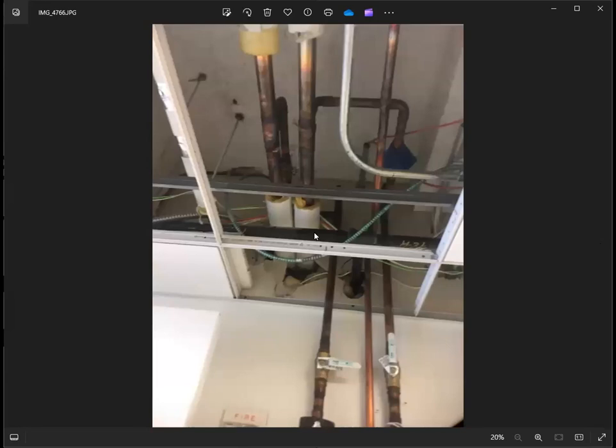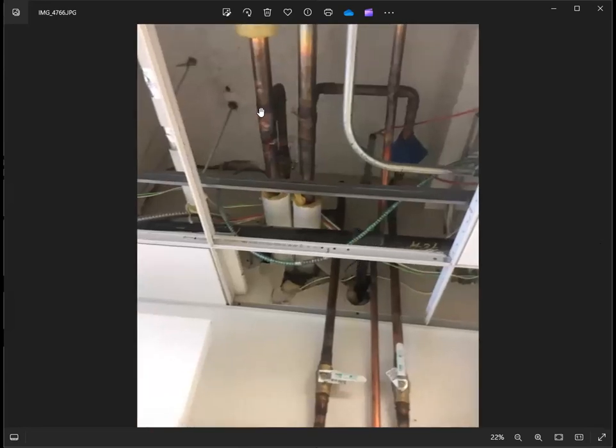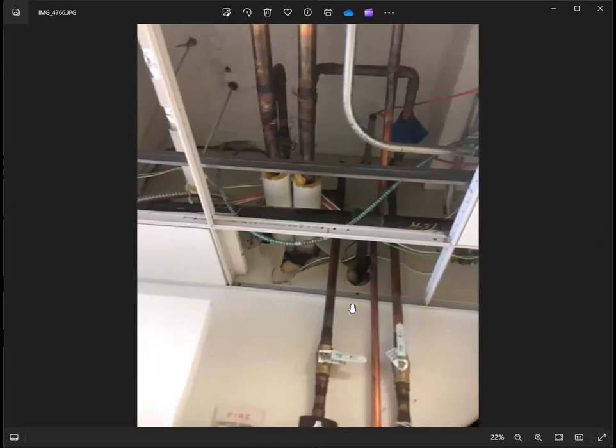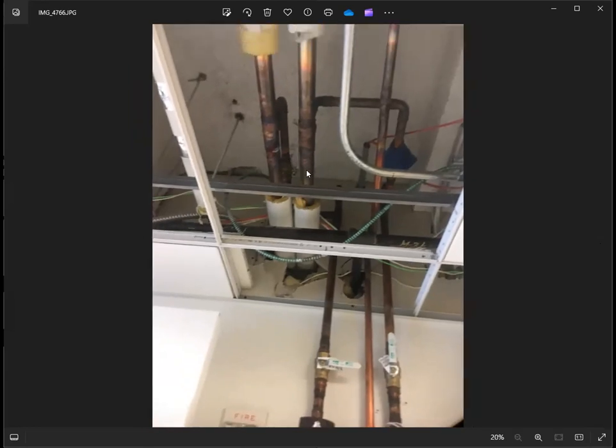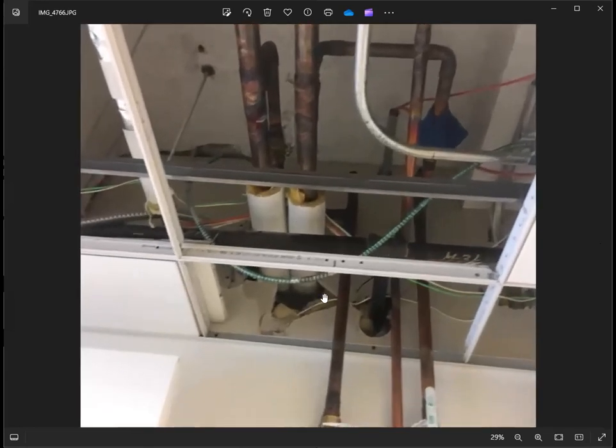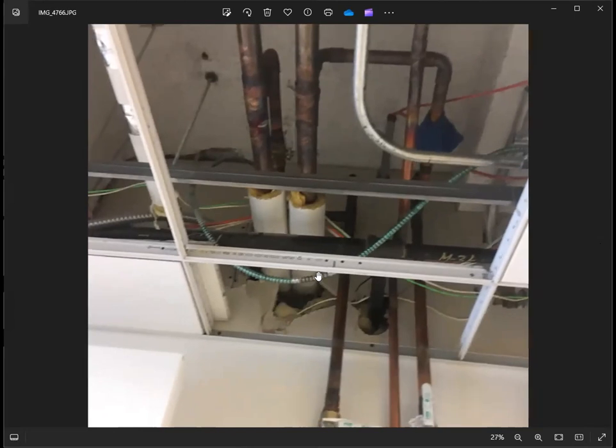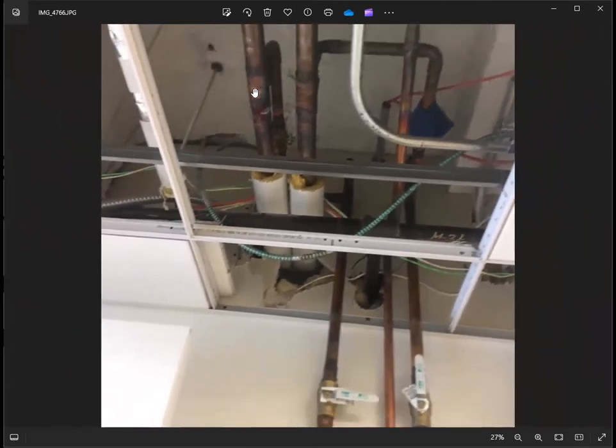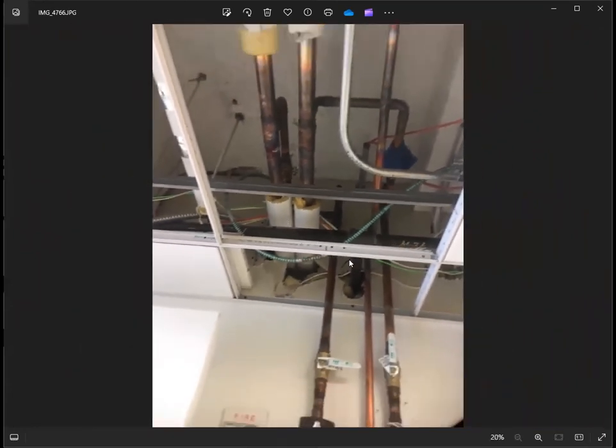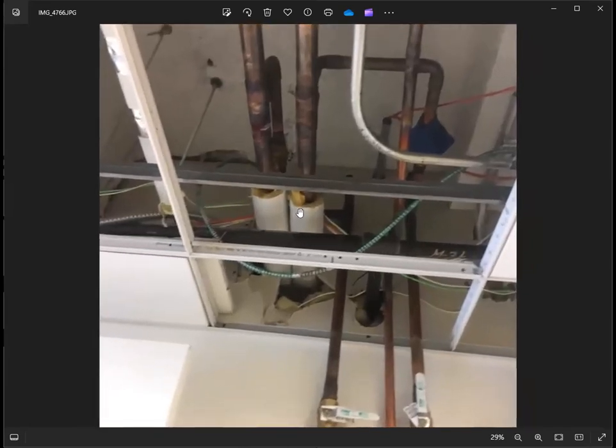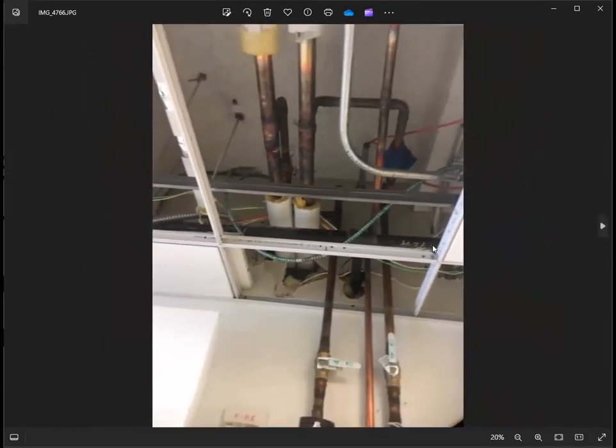Same. And this is the copper piping. So this is the branch that goes to the unit. Probably this is an existing or a new one as per drawing plan. So all these penetrations are new. So if you're gonna do firestopping, they need to restore what was previously rated, especially if this is a rated fire wall. So they need to close all those gaps that occur during the installation. And take note also of the installation of the pipe. They need to complete the installation.